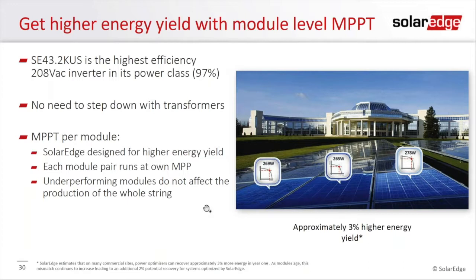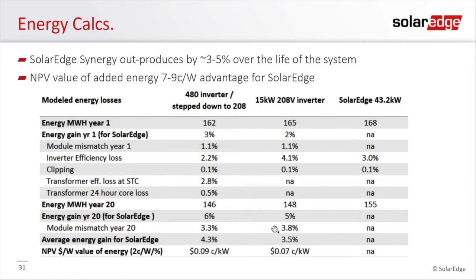So why do we produce more energy? It's pretty straightforward. We have a power point tracker effectively on every module, and what we're able to do is overcome module mismatch. That is the key part for SolarEdge, even looking at applications here. In this example, the 100 kilowatt on this apartment building, we're assuming no shading and no different angles or orientations. Everything is pointed in the same direction. Essentially, what we typically see is an average of about 3% higher energy yield using SolarEdge in those situations.